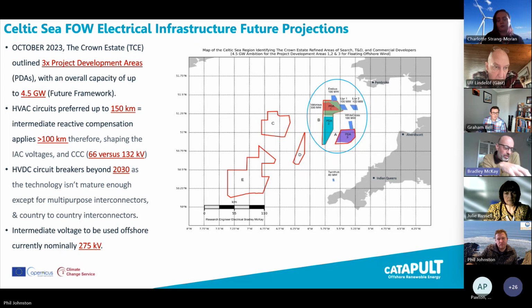But I think the big thing that really came out for me was these losses. We've got 4 fundamental, huge losses that occur in alternating current: your core loss, your screen loss, your dielectric loss, and your armor losses. And modeling that over a 20-kilometer period, if we put a string together, we started to see roughly about 0.9 of a gig in relation to losses within this AC system.